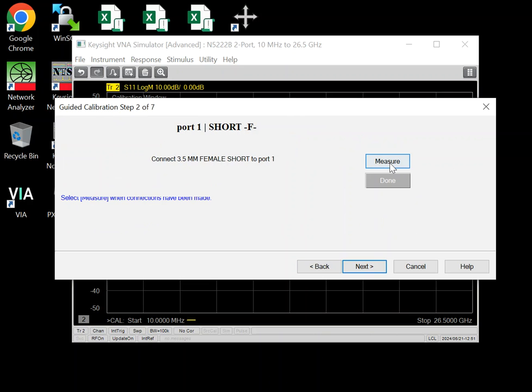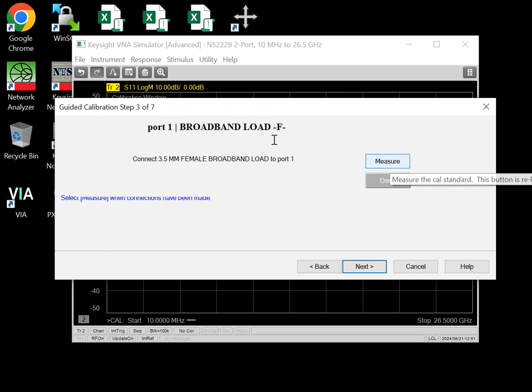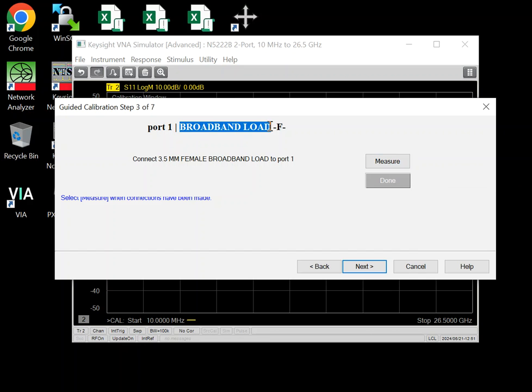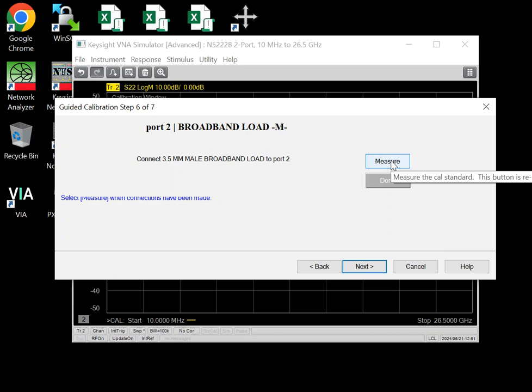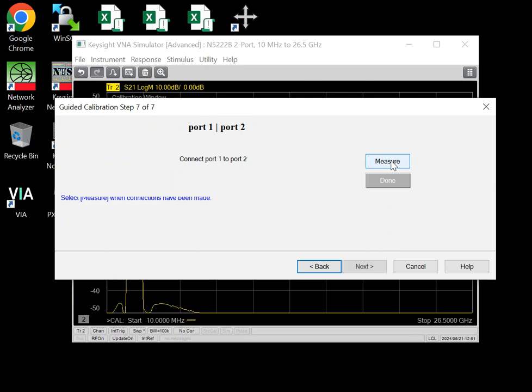So you do open, short, and here take the broadband load out of your kit. Your kit has both a low band load and broadband load. So make sure you pick the broadband load. And then you do again open, short, broadband load.